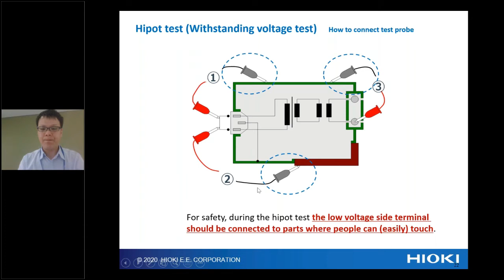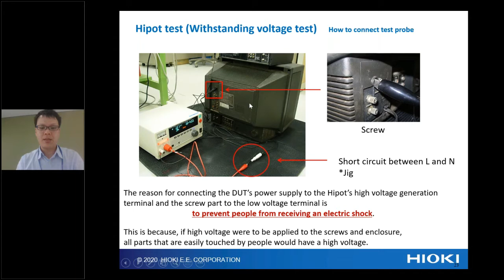This is one example of a measurement on a TV for Hipot. This is a TV. The red probe carries the dangerous voltage that this instrument will apply. So the red probe connects to the short circuit between L and N. It's a jig. The black terminal we can connect to a screw, because when someone touches around here, it is safer than the reverse connection. That's why we recommend connecting like this picture.